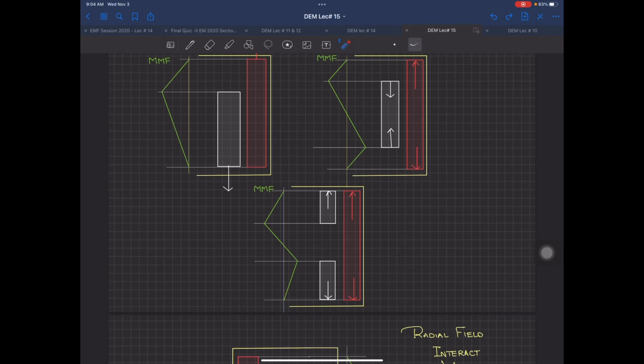The current is huge, 630 amperes, 500 amperes. ये करंट आपको वहाँ नहीं मिलेगा in a generating station transformer or a transmission line transformer, because here the current is being squared. So distribution transformer के ऊपर ये forces ज़्यादा problematic हैं, because the current value is large over there, because you are going on up to the level of 400 volt or 230 volts over there.